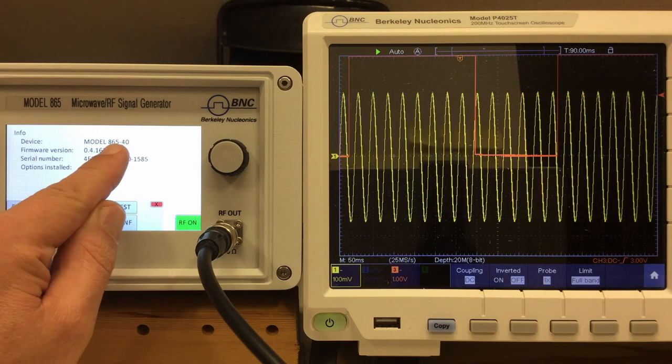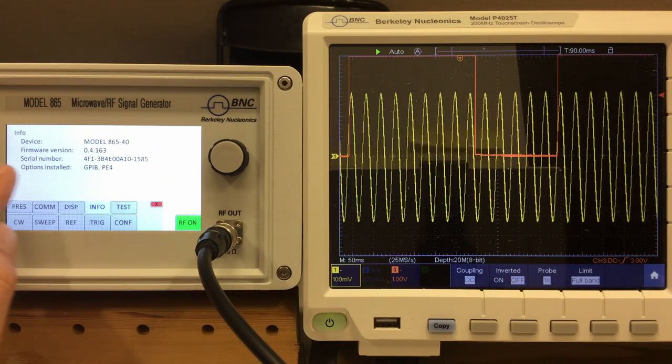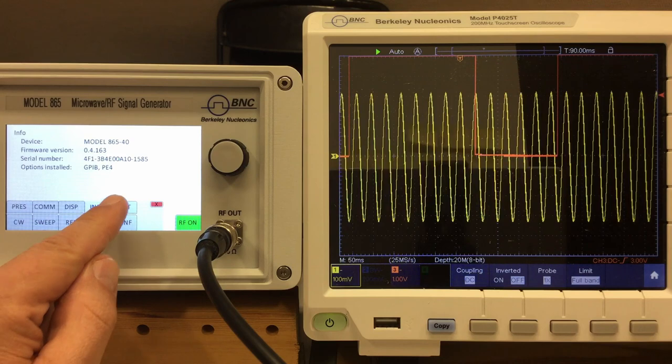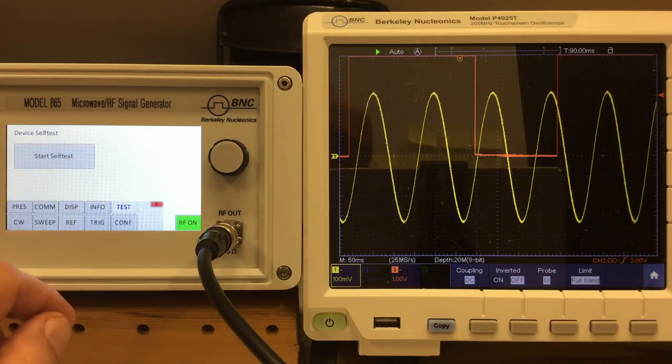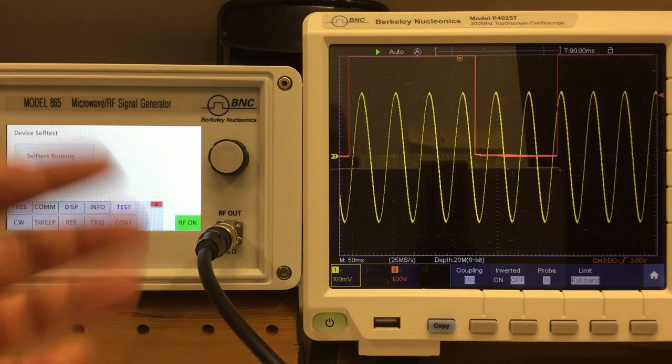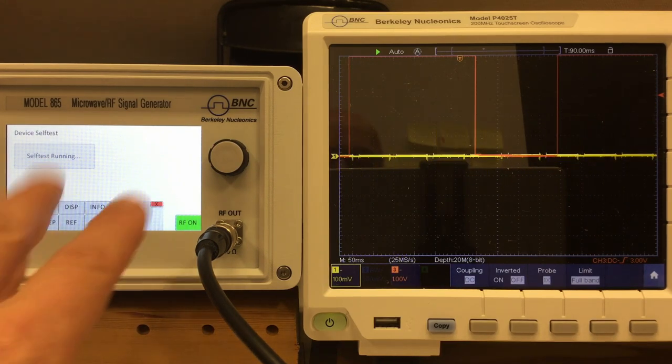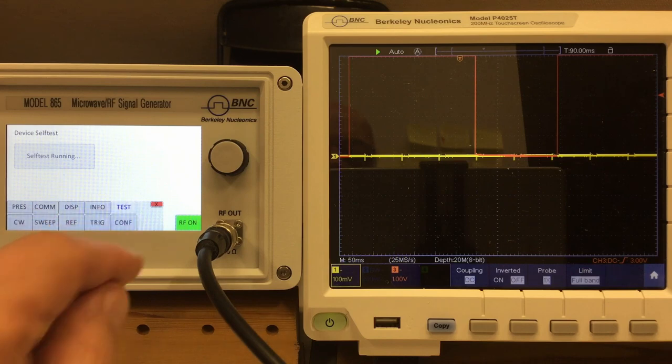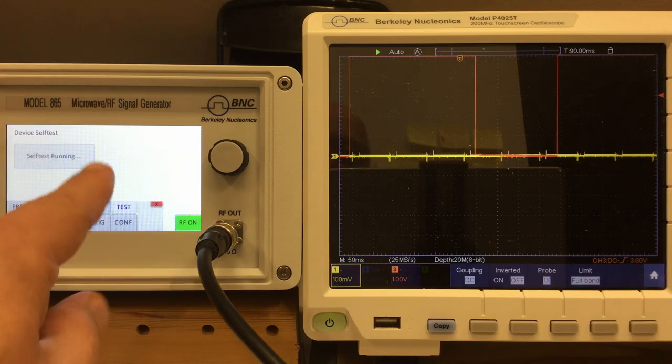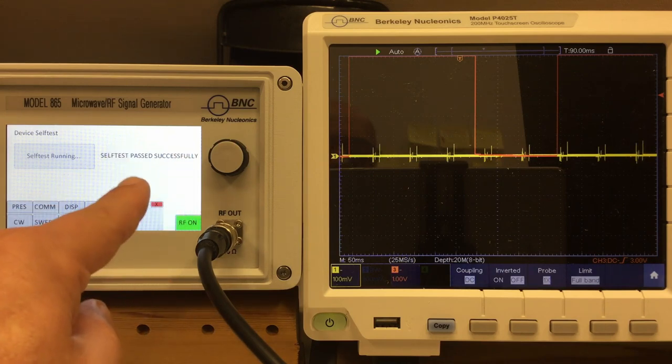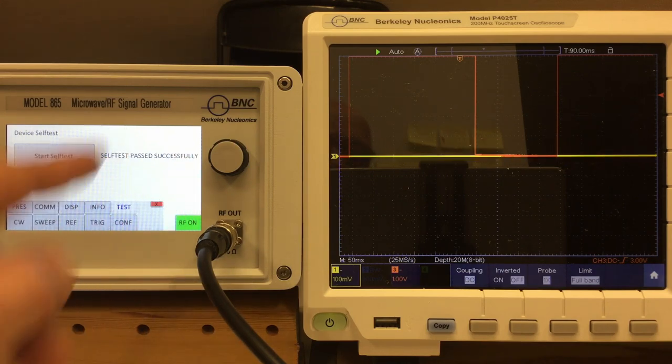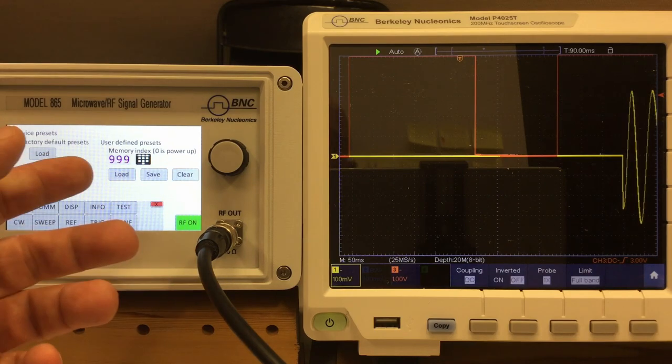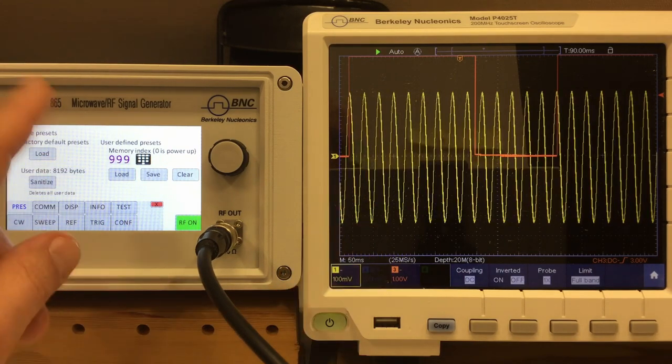Now, info, basically the same information you already seen when booting the device. The model number, 865-40, 40 GHz, firmware version, serial number, and the options installed. And of course, there is a test. To be more specific, a self-test, and we can start that, and it doesn't take too long. Oh, I lost a little bit of my camera here. I got a moiré. Worse than normal, but you can see what's going on. And it should be over in a few seconds. Yeah, a self-test passed successfully. And after you do a self-test, you better go back to your presets and load your stuff again. And you're back in business.